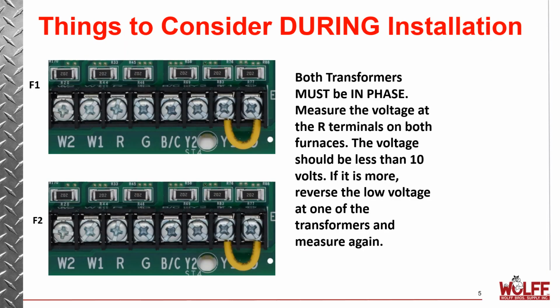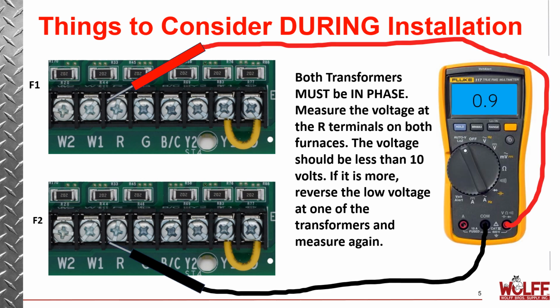Now that our high voltage is wired, we need to check our low voltage. Both transformers must also be in phase. You're going to measure the voltage at both R terminals on each board. The voltage should be less than 10 volts. If your voltage is higher, you're going to reverse the low voltage at one of the transformers and measure it again.